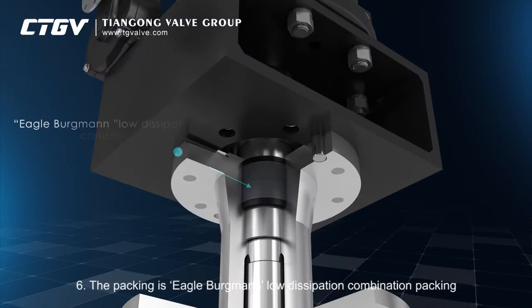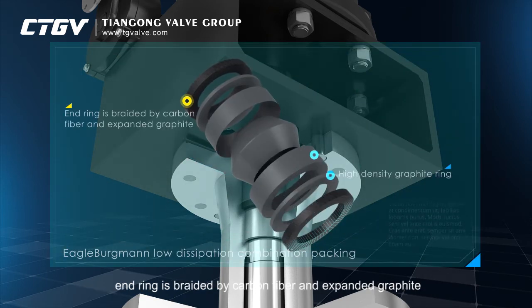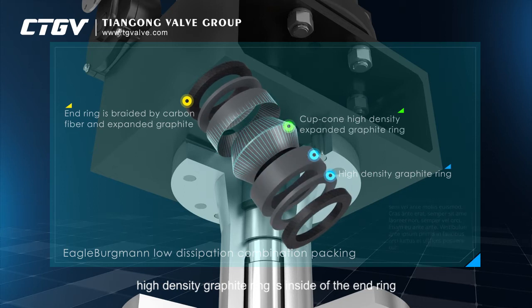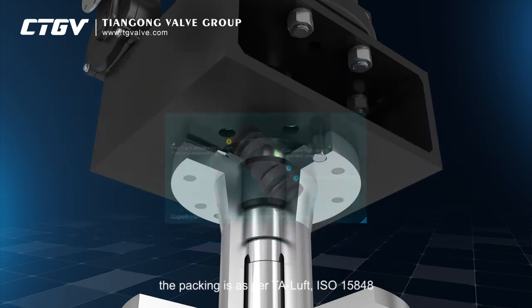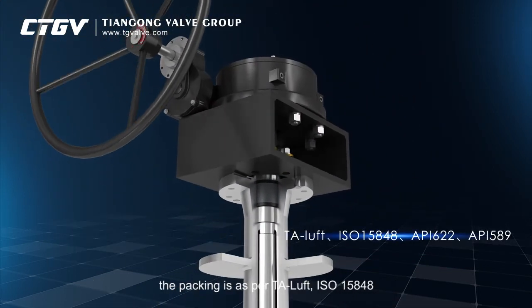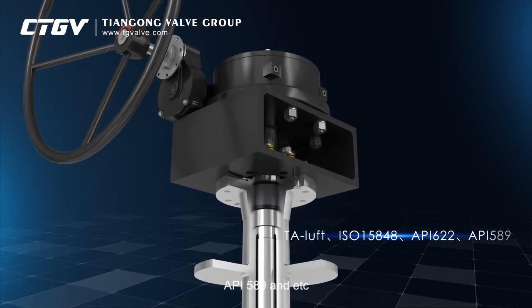6. The packing is EagleBurgmann low dissipation combination packing. The end ring is braided by carbon fiber and expanded graphite. High-density graphite ring is inside of the end ring. There is a cup-cone high-density expanded graphite ring in the middle. The packing is as per TA Luft, ISO 15848, API 622, API 589, etc.